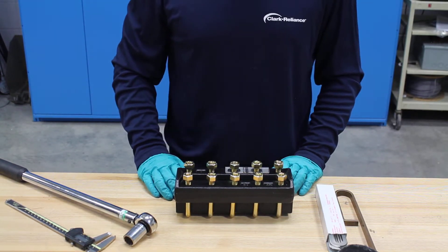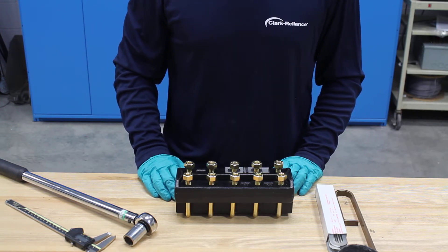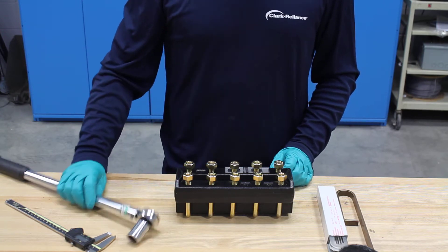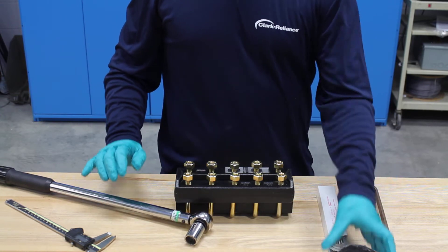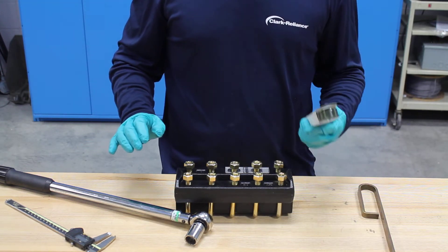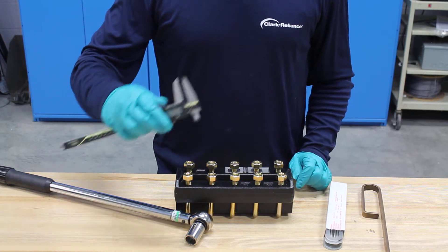Today we are going to demonstrate the best practice for maintaining and rebuilding a Jerguson Series 20 armored reflex gauge. The tools you will need to perform this rebuild are a calibrated torque wrench with three-quarter inch socket, a brass scraper, Molykote or similar lubricant, a glass rebuild kit consisting of new glass and gaskets, and a pair of calipers.